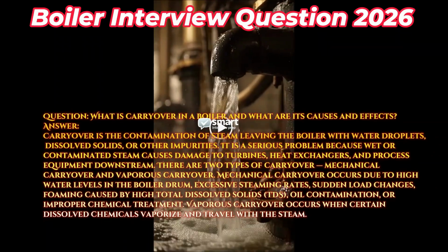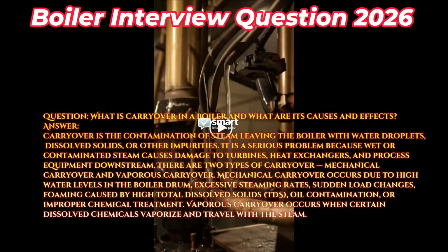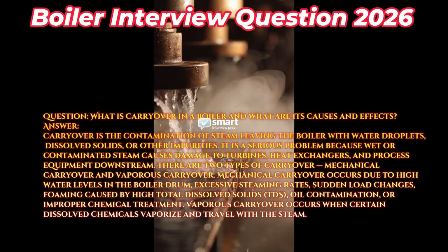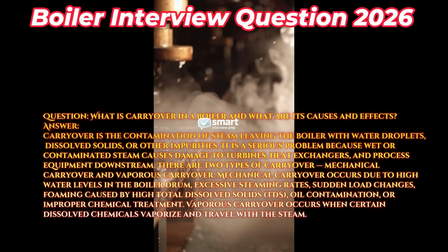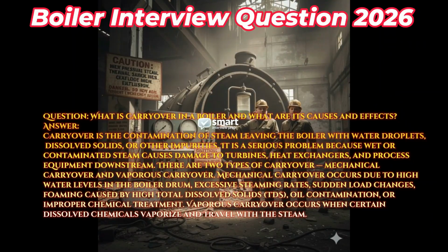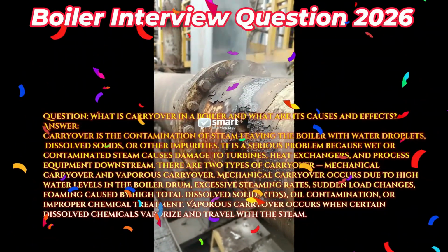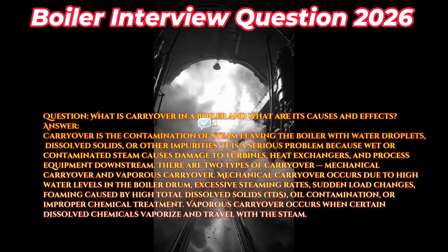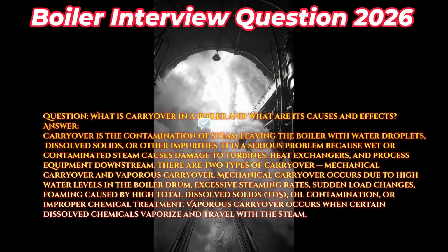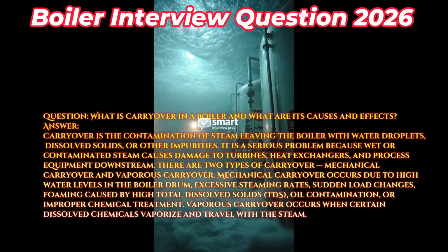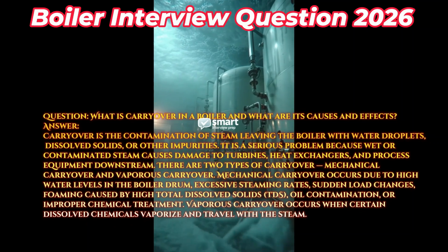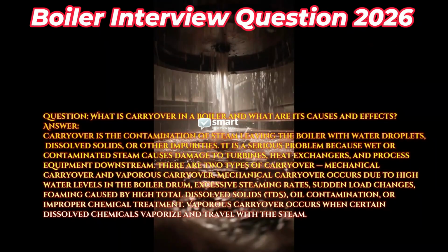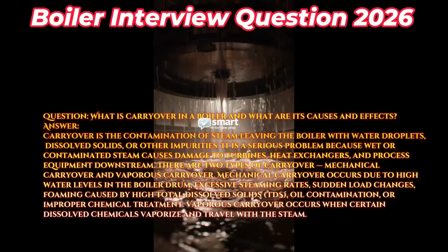Answer: carryover is the contamination of steam leaving the boiler with water droplets, dissolved solids, or other impurities. It is a serious problem because wet or contaminated steam causes damage to turbines, heat exchangers, and process equipment downstream. There are two types of carryover: mechanical carryover and vaporous carryover. Mechanical carryover occurs due to high water levels in the boiler drum, excessive steaming rates, sudden load changes, foaming caused by high total dissolved solids, TDS, oil contamination, or improper chemical treatment. Vaporous carryover occurs when certain dissolved chemicals vaporize and travel with the steam.